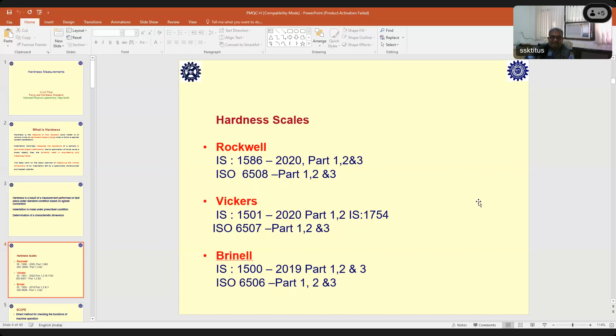Now, the scope of our talk will be mainly the direct method for checking certain functions of this machine, how we have to see the machine, whether the machine is really in a position to calibrate the blocks. And all the machines which are calibrated can also be checked by an indirect method. So whenever we are using a method for calibrating the hardness block, we have to check the performance of the machine both directly and indirectly. For direct measurements, we need to calibrate the forces, we need to calibrate the indenter's geometry, and we have to also calibrate the machine for its timing cycle.